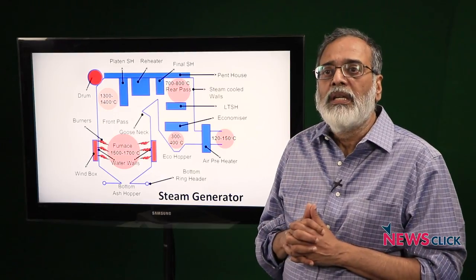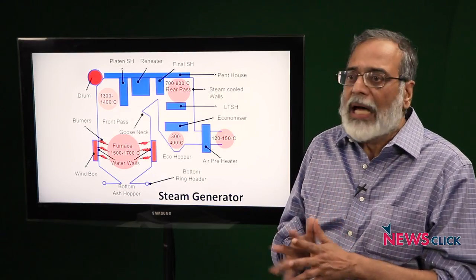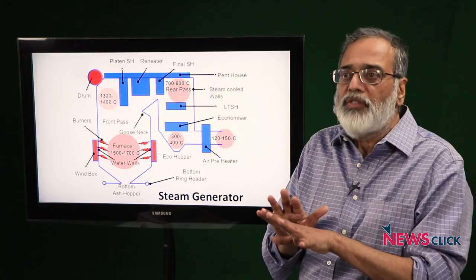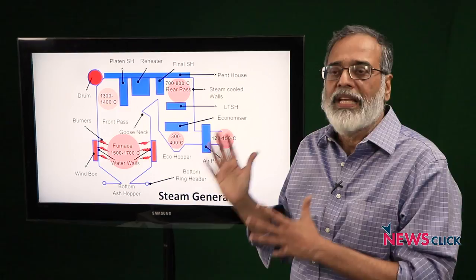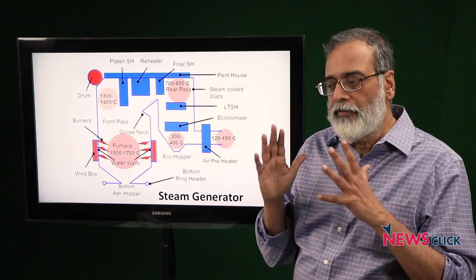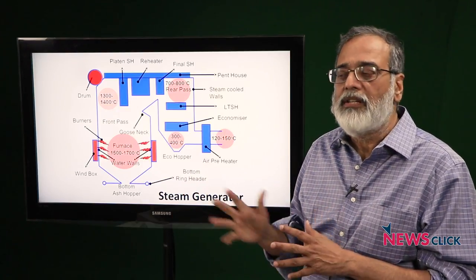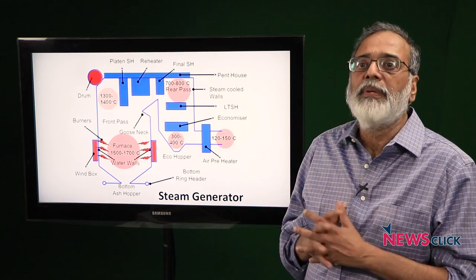The question to ask is, should this have happened? The answer is clearly no. If these safety precautions had not been bypassed, there is no way such an accident could have happened. Should this boiler have been maintained under such conditions where it was clinkering? Should manual attempts of double poke, which is known to be dangerous, have been part of the procedure? Should the bypass have taken place of vital protections of the boiler?